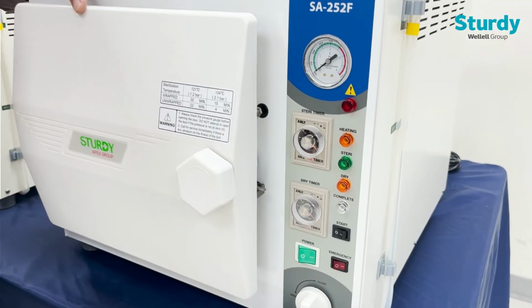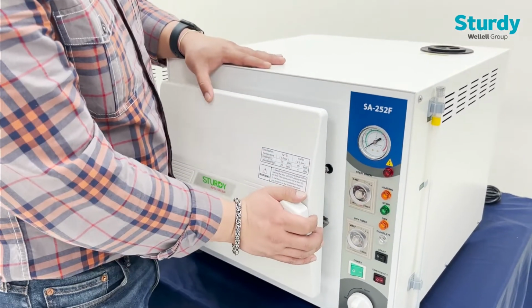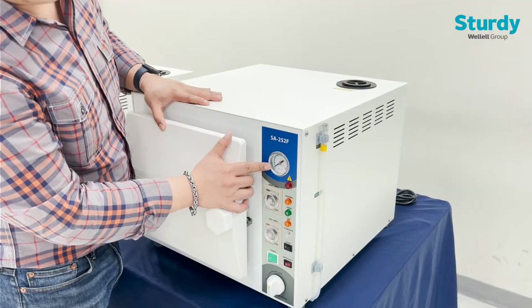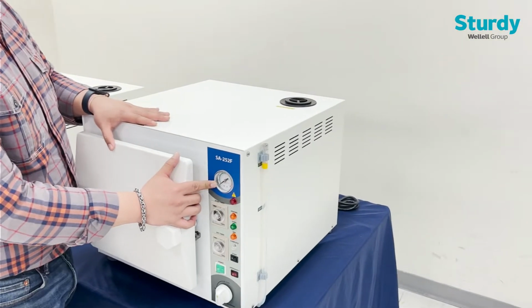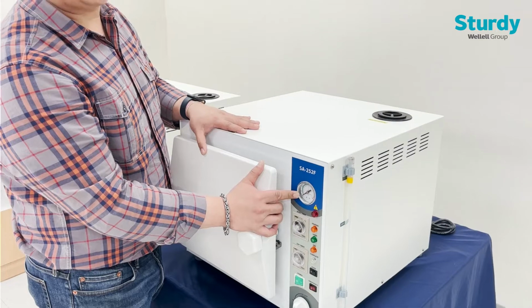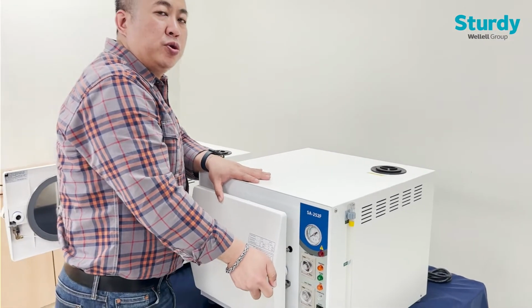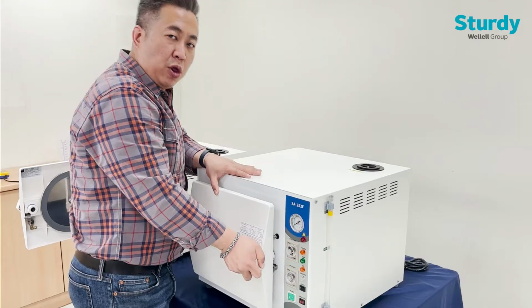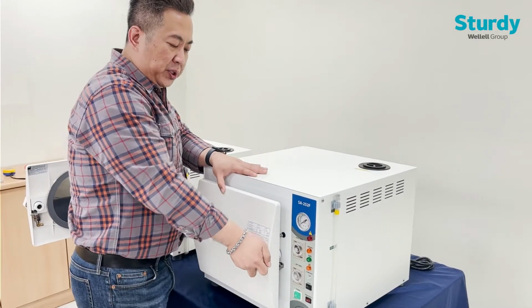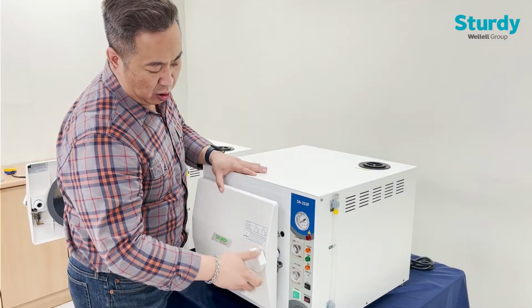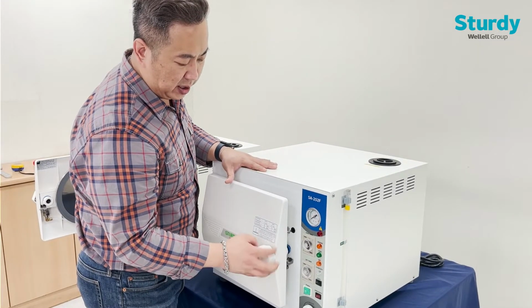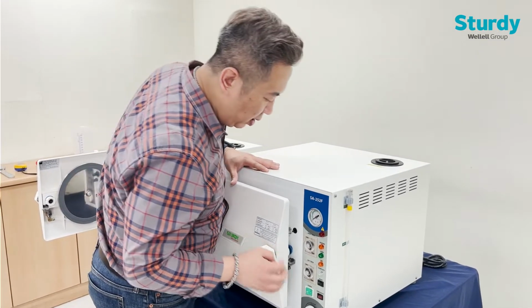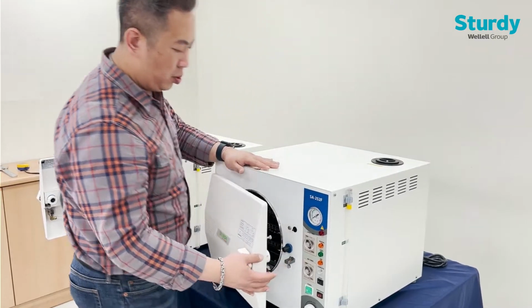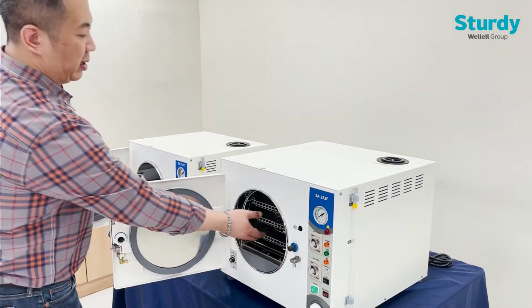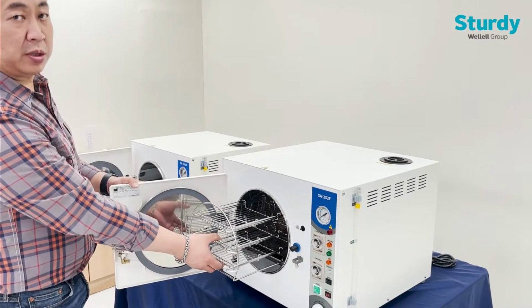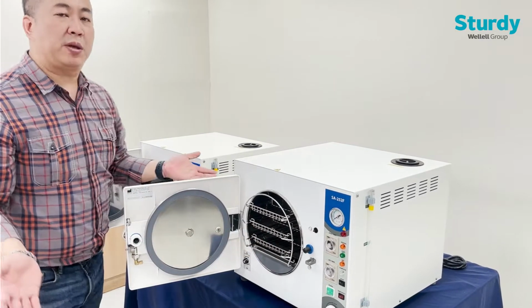Once it comes to the end of sterilization, before opening the chamber door, please ensure that the internal chamber pressure is at 0. Otherwise, the chamber will not open, as the handle is locked. Loosen the handle and turn anti-clockwise right to the end. Once it's fully loosened, lift up the safety latch, open the chamber door, and then we remove the sterilized objects. And your sterilization is complete.